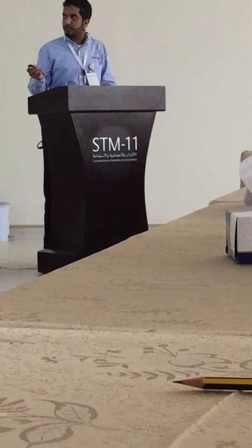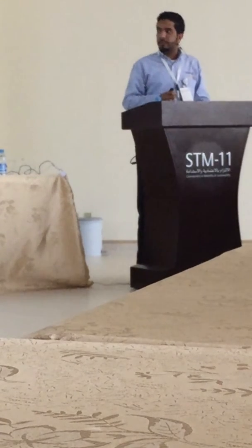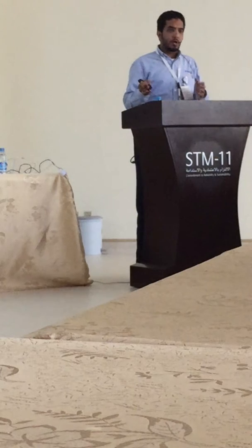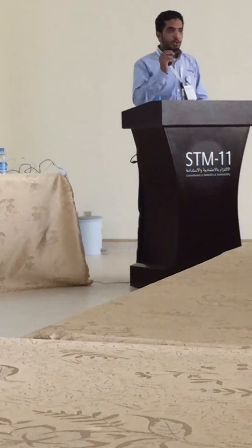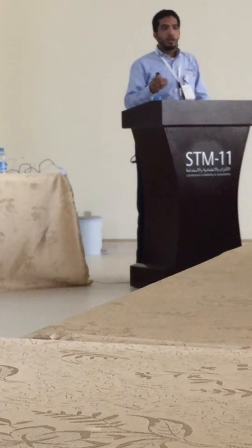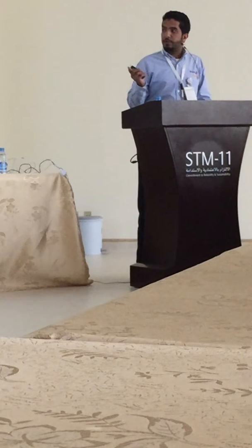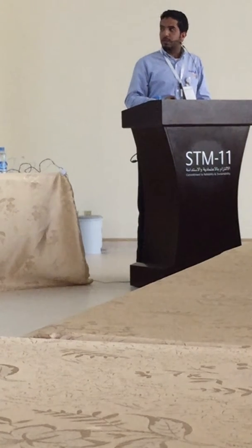The third thing is to overcome difficulties faced at this stage. Examples of such are, as we said, flow rates or temperature of streams in case of branch lines, instrumentation absence, and multi-phase streams. That is overcome by intensive study of the system to derive a measurement tool. We go back to the P&ID detailed study where we can find the parameters that we can use to do this calculation, along with going to the field, tracing the line, and making sure they are the same as in the P&ID. Variation of HTC with variation of flow rates to the heat exchanger.